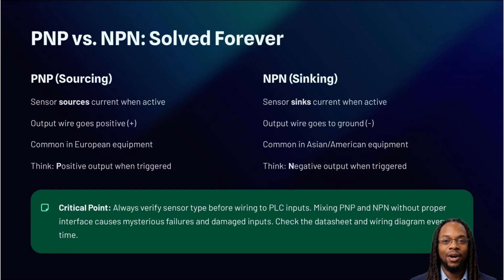I want to take a full minute to talk about one specific concept that trips up almost every single beginner: PNP versus NPN sensors. This refers to how the sensor switches the electricity. A PNP sensor is sourcing. That means when it activates, it sends the positive 24 volts down the wire to the PLC. Think P for positive. An NPN sensor is sinking. When it activates, it connects the wire to the ground or negative side. Think N for negative. Here is why this matters. If you buy the wrong replacement sensor, say you put an NPN sensor on a PNP input card, it will not work. Worst case, you could create a short circuit and fry the input module. Always check the part number in the data sheet before you wire it in.